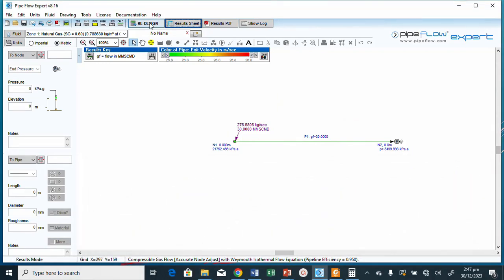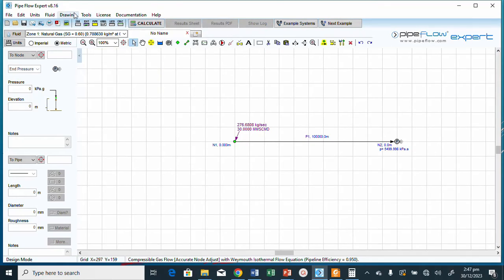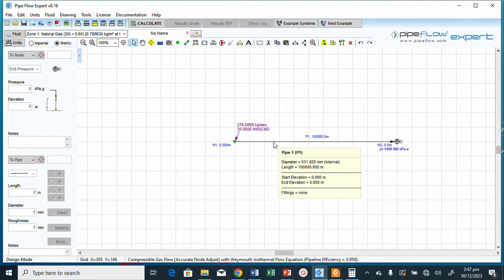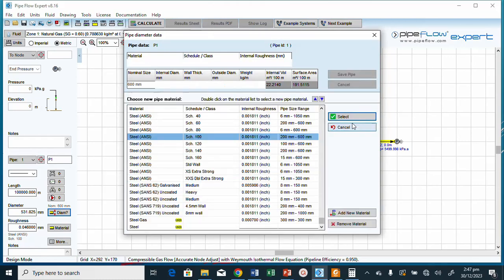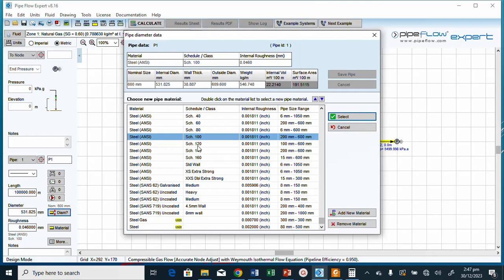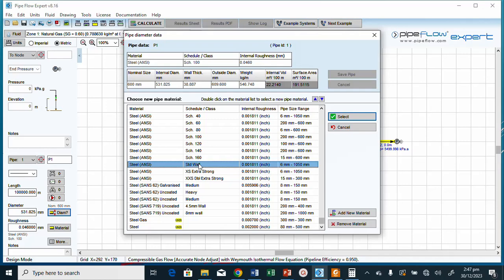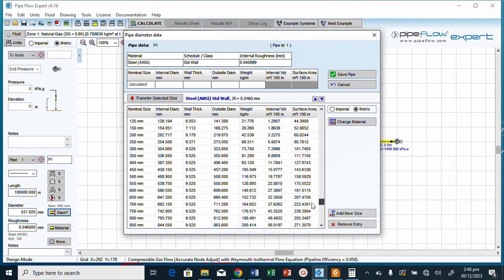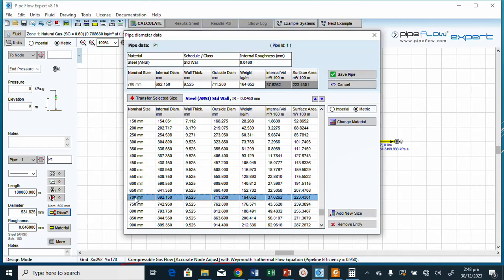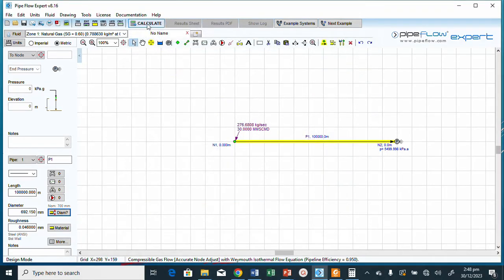We need to select a larger pipe. Let's go to the pipe selection again. The 600 mm size didn't work. Let's look at the schedule — using standard steel pipe which has sizes from 6 mm to 1050 mm. We'll move from 600 mm to 700 mm.